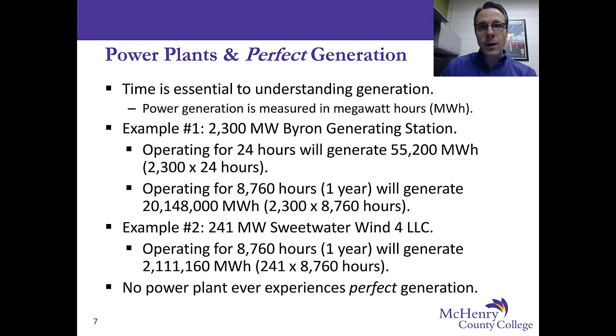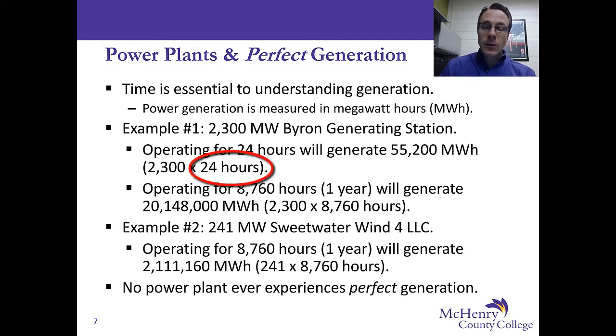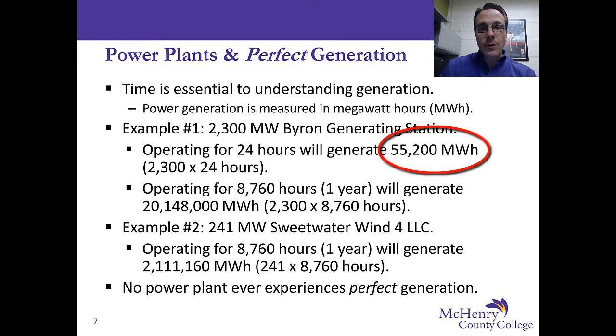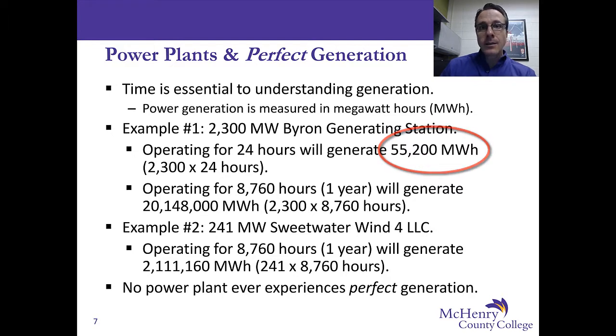To calculate generation, it's a simple multiplication problem — nothing more complex than that. Using the Byron Generating Station as an example: we have its capacity of 2,300 megawatts, and if we run that plant at 100% for 24 hours, we simply multiply its capacity by 24 hours and we get an electric output of 55,200 megawatt hours. Notice that hours is included — we can't talk about electricity generation unless a unit of time is included.